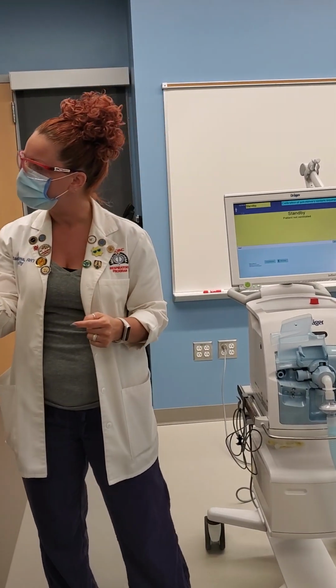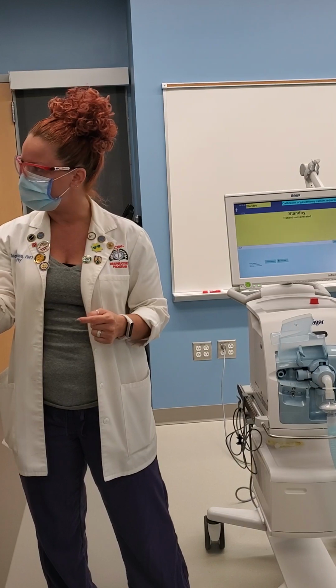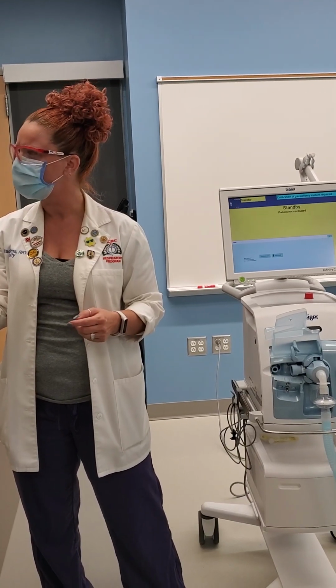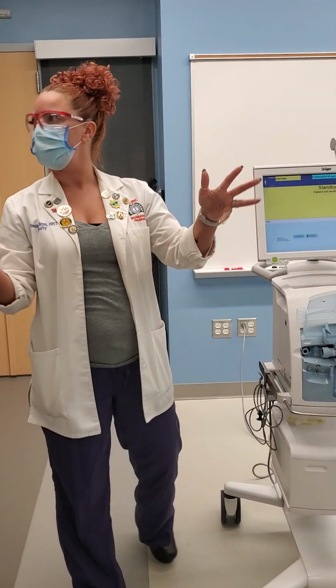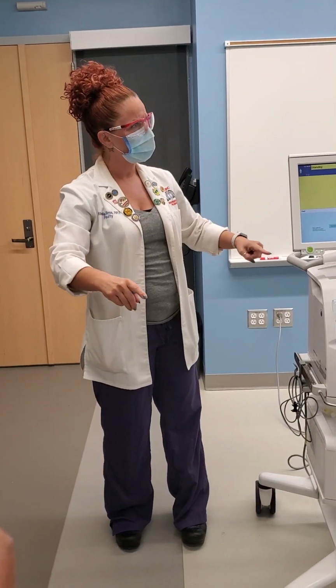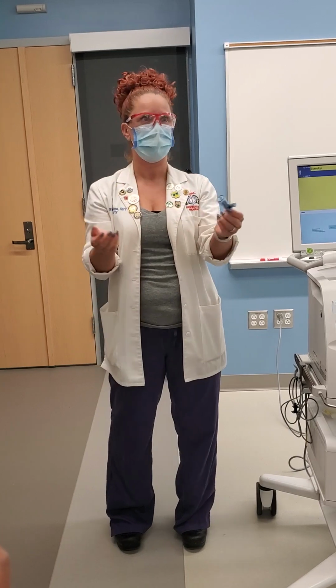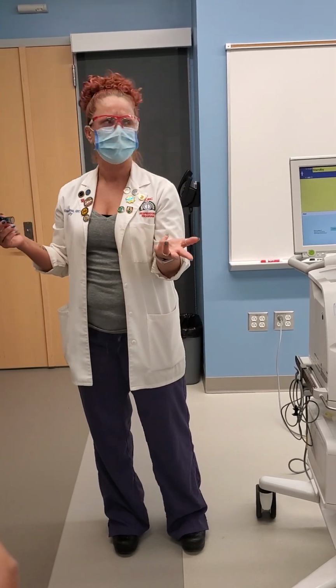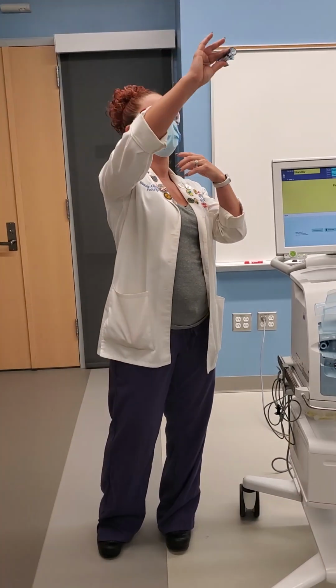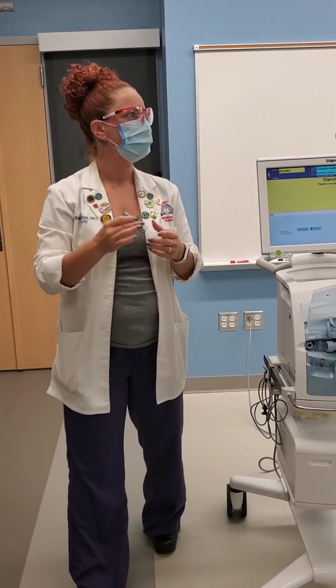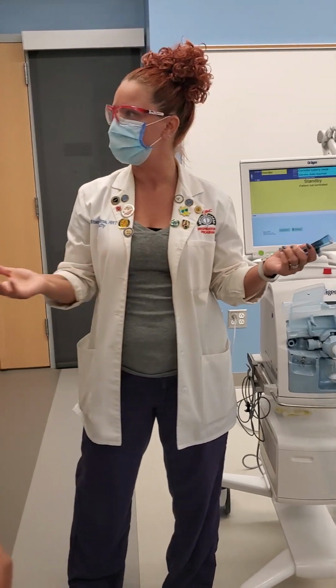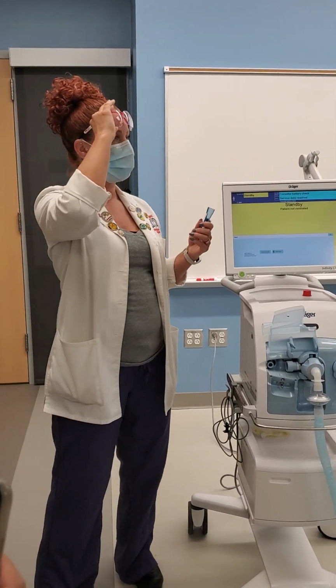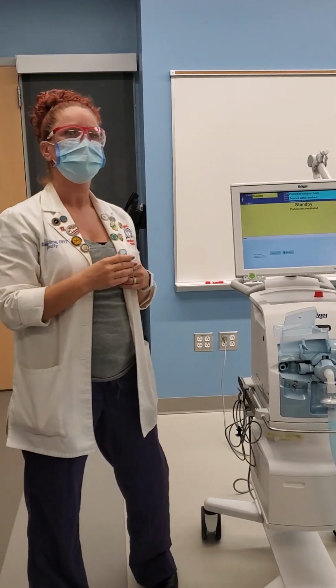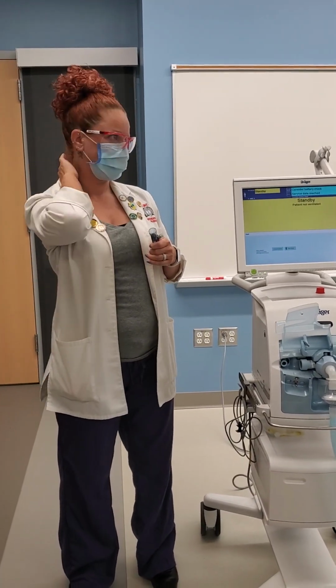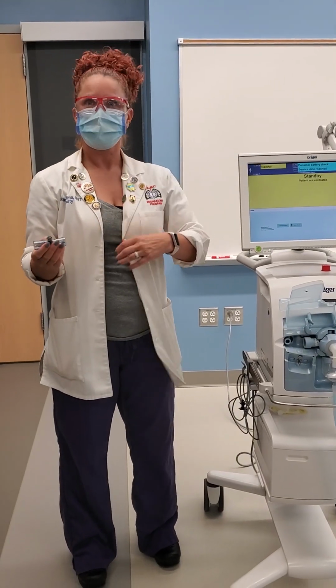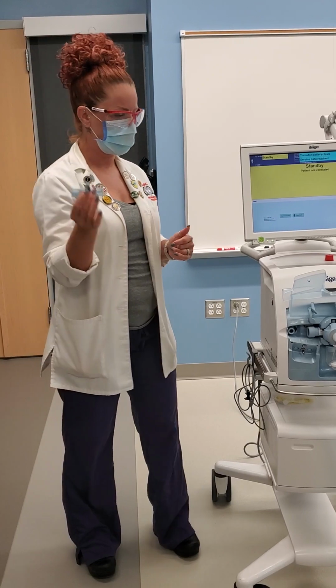Do you autoclave these? They clean those. Do you do it? I bring it down to sterile processing. Some places have an autoclave where you put it in there and you turn it on and it gets to certain temperatures and kills bacteria. But the issue is those filaments. Everybody thinks that they shouldn't be in there. The people down at sterile processing clean it so that they get rid of it because they think it's fuzz or something. And that completely destroys it, and you can no longer use it. Now you have to get a new one that costs several hundred dollars. Yeah, these are expensive.